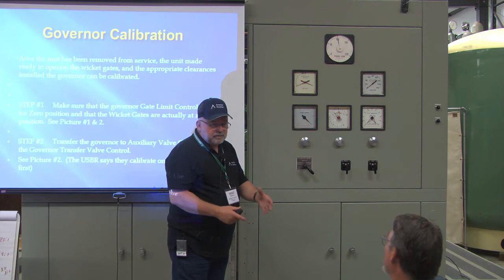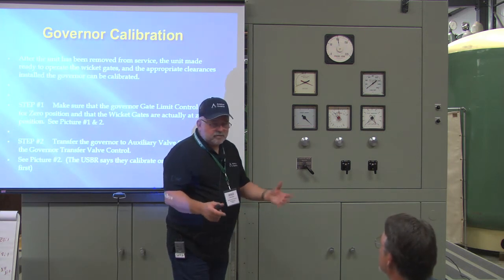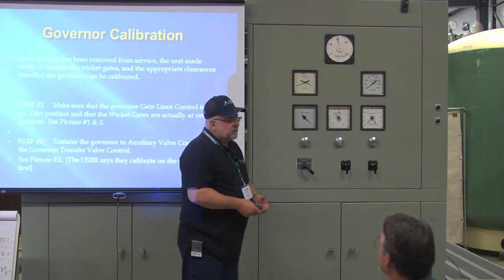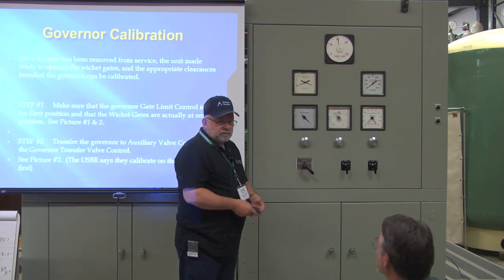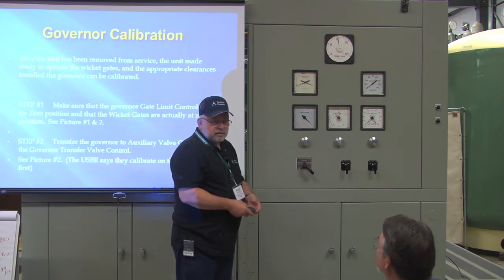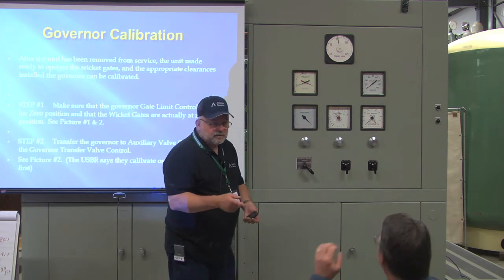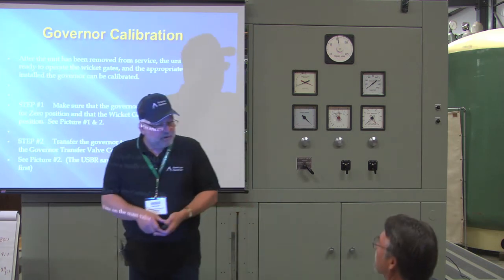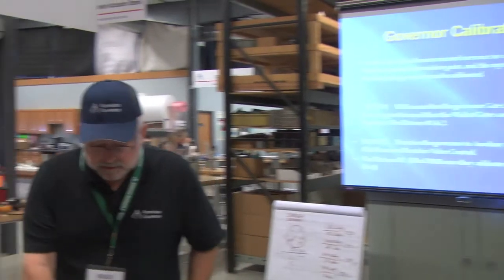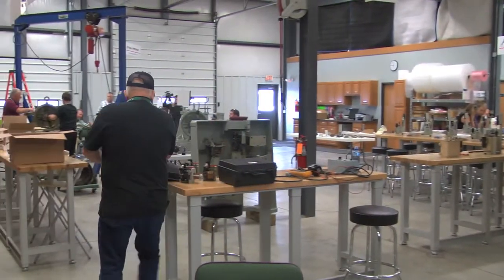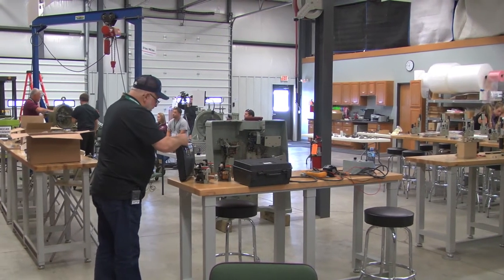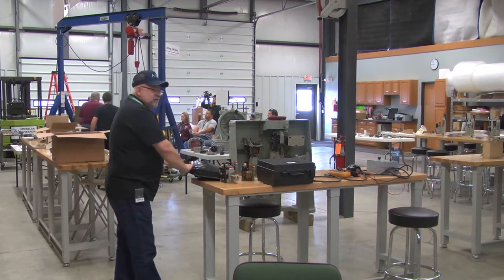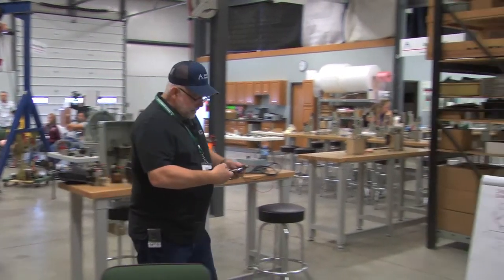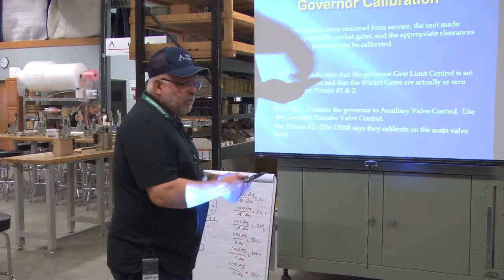What's the speed of your units? 81.8. Okay, so they're slow speed machines. You got about 80 poles? Oh, I couldn't tell you. Well, what was it? How much? 81.8. 81.8 RPM? Show you how to do that. Any 60 cycle system, all you need to know is how many poles or what the speed is.